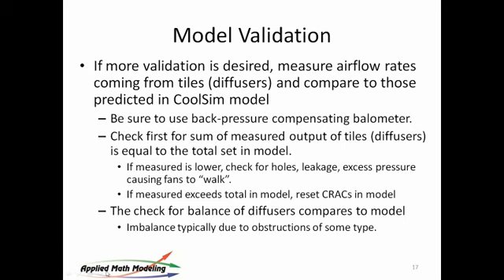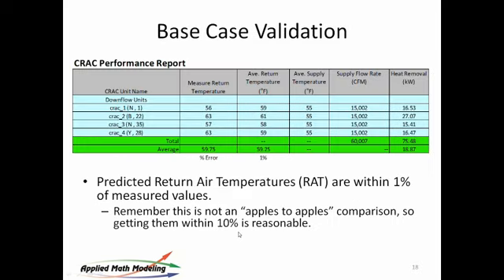And generally, we find these line up quite well. Now, in this case that we are looking at today, there are 4 CRAC units. I set the supply temperatures to be 55, and this is coming right out of our summary report that's produced as a result of the output. The average return temperatures... These were measurements from the client side, too.